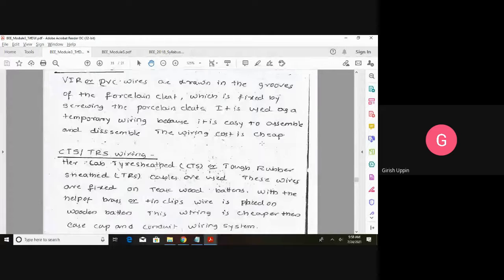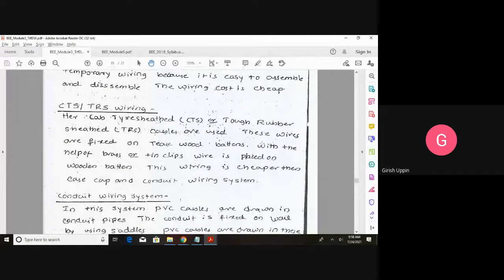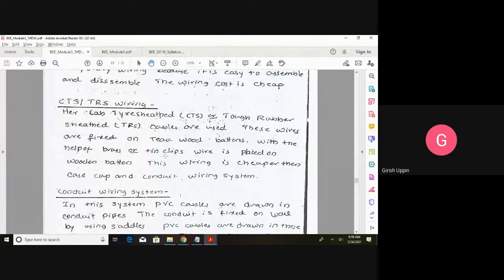In the case of CTS or TRS wiring, the wires are fixed on teak wood battens with the help of thin brass clips. The wire is placed on a wooden batten. This wiring is cheaper than casing and capping and conduit wiring. If you have visited villages, you might have seen this type of wiring. There is a wooden piece, the wires go on top of it, and a clip holds the wire to the wooden piece. That type of wiring is called CTS or TRS wiring.